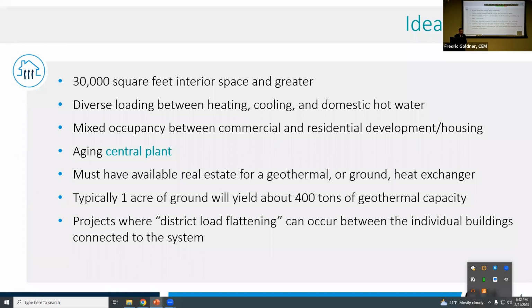In order for a geothermal system to work, we have to have what's known as a balanced load. We can certainly drill enough boreholes, or geothermal holes, in the ground to match a specific load, whether it be heating or cooling, but we really don't want to go in a direction that's away from the balance point. For example, if I have a heating dominant building, would I drill more? Would I spend the capital to drill a geothermal bore field that matches the capacity of the heating system, or drill it to match the cooling capacity of my building, plus a little extra for contingency?